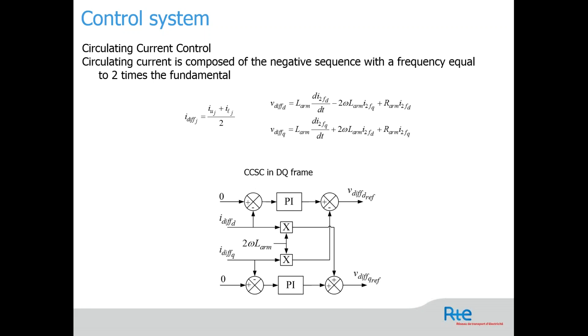So usually in HVDC, the usual way is just to eliminate or suppress this circulating current. There are other, fancier types of control systems for the circulating current, but in this working group we decided to go with a simple control, as shown here. The I_diff is the circulating current control, the differential current, and when you write the equation you end up with 2 PI controls. As I mentioned, in this case the circulating current reference is set to 0. In this way, we achieve zero circulating current in each phase of the MMC.